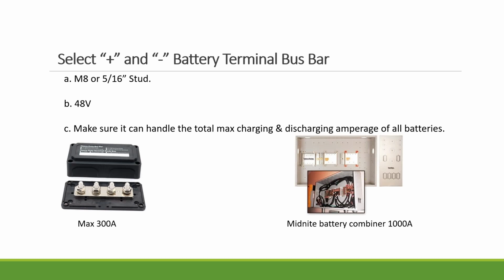If you want to parallel multiple batteries, we always suggest that you use a bus bar, and there are a few things you want to make sure of. You can hook up with an M8 terminal ring. It's a 48 volt rating, and then you look up the maximum charging and discharging amperage of the battery, and decide how big the terminal bus bar needs to be. Some customers also make their own bus bar, which can be very inexpensive. If you go with a Midnite, it's nice, a little bit more pricey, but you can also make your own.